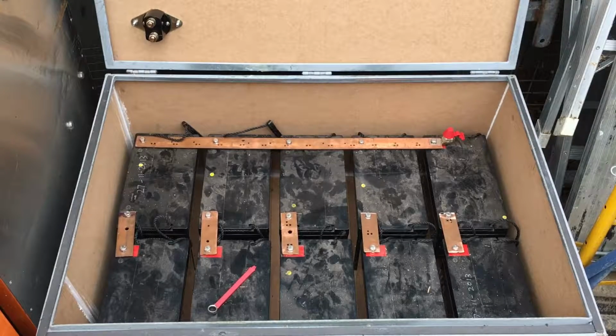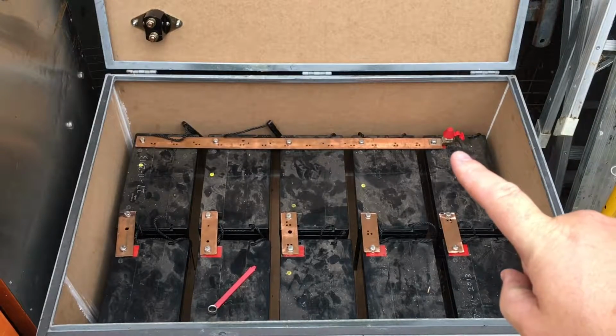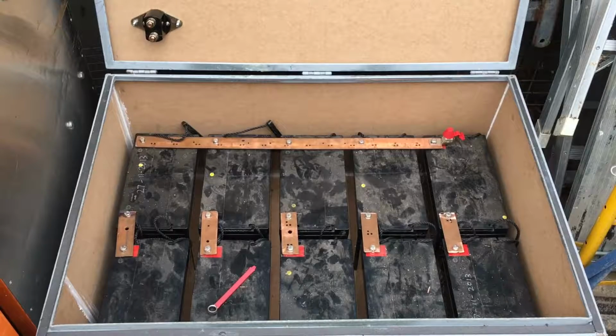As you can see, these batteries are wired up for 24 volts. I've got some 40mm wide, 3mm thick copper bus bar to do that, which I got from the scrapyard, so cost is obviously a consideration. I also have a 300 amp fuse on the positive leg, which will go from the positive leg of the battery to the switch, and then into the switchboard, so it can be taken apart and relocated to the farm and set up for the cabin.